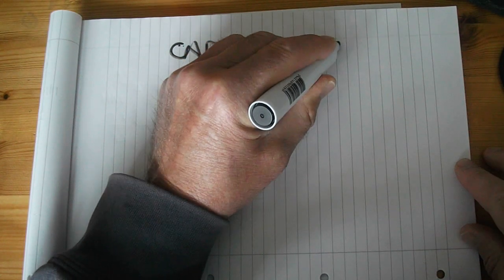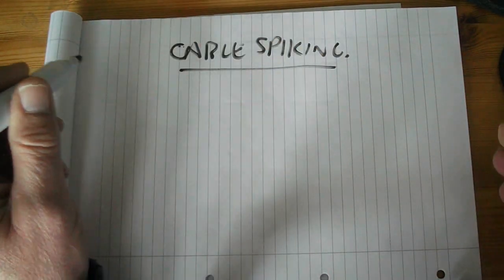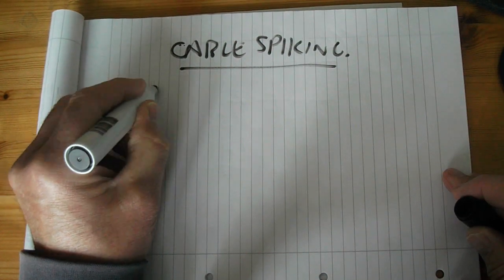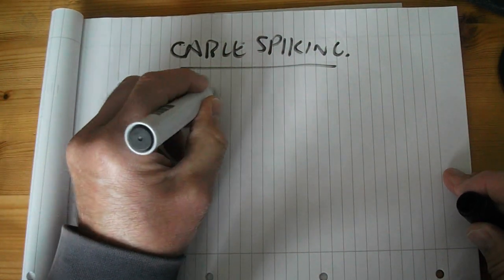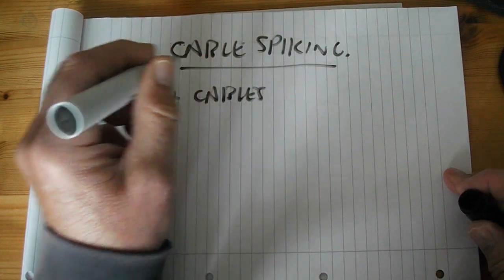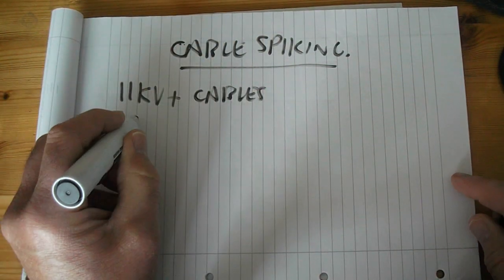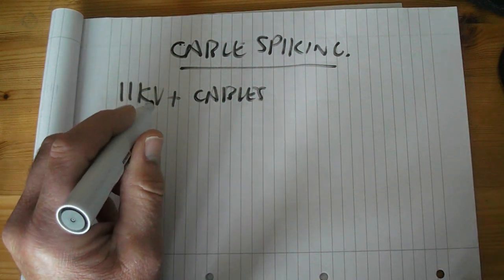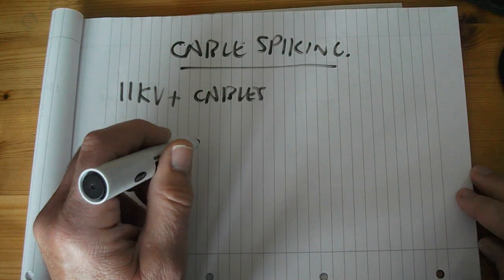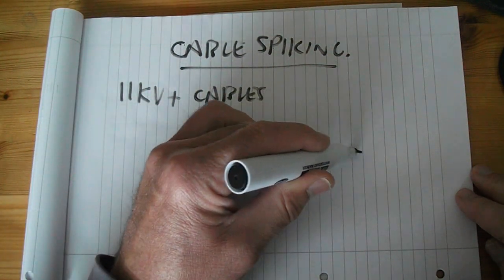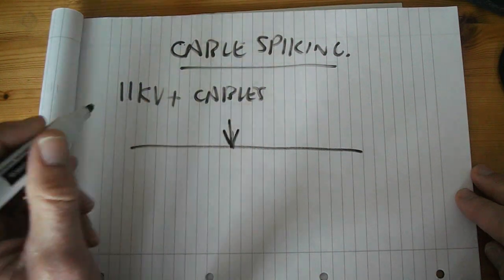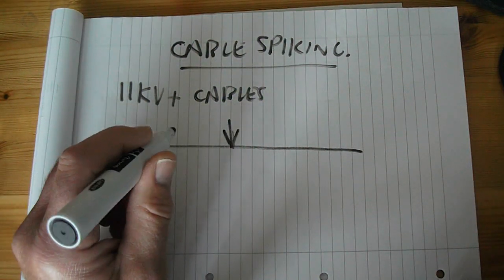Morning all. What we're going to have a look at this morning are a few items on substations, and I want to talk about cable spiking. What this is about, with 11 kV plus cables, they have to be proven to be dead. And the only way to do that really is to what we call spike the cable.